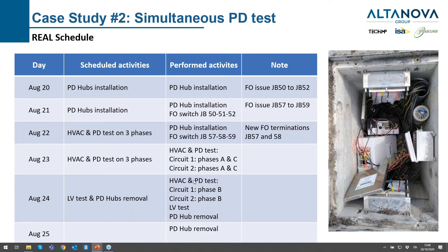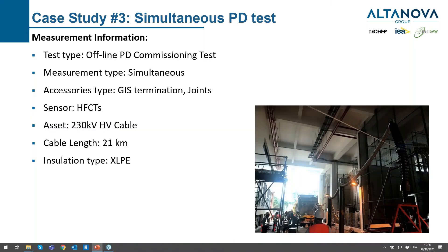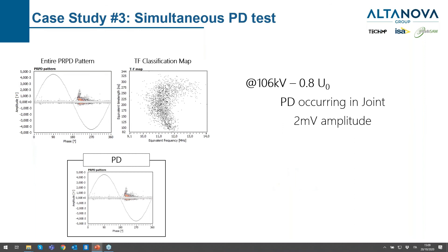It was a big relief for the utility to complete this huge job without a lengthy outage and in a very straightforward way, with six engineers connected via the fiber optic network to the acquisition points. Another long-circuit simultaneous PD test was an offline commissioning test on a 21 km cable with GIS terminations on both sides and joints in the middle, using HFCTs. A permanent monitoring system was already installed, and its hardware was used to perform the offline spot testing.